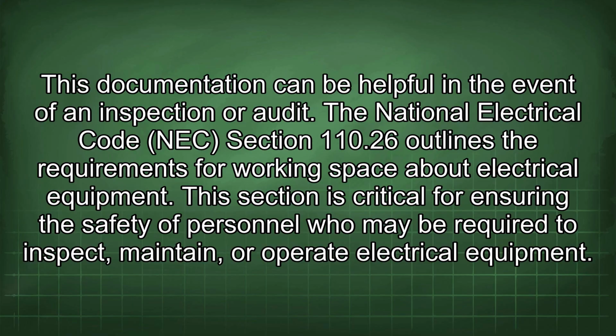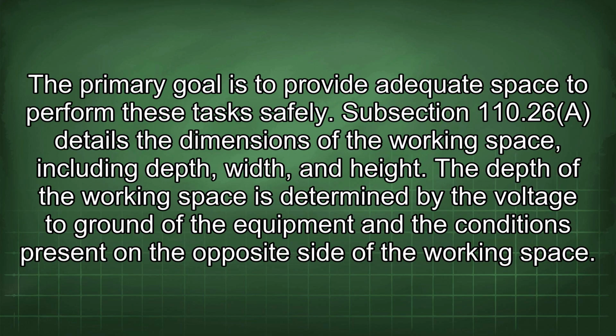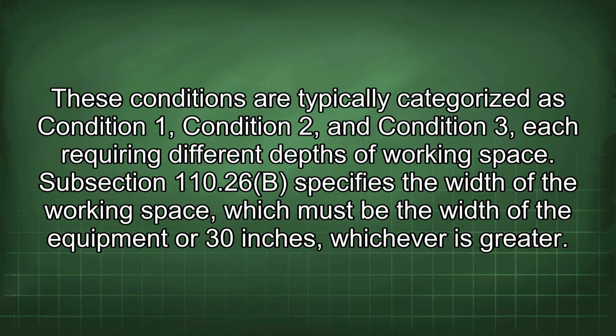The National Electrical Code, NEC Section 110.26, outlines the requirements for working space about electrical equipment. This section is critical for ensuring the safety of personnel who may be required to inspect, maintain, or operate electrical equipment. The primary goal is to provide adequate space to perform these tasks safely. Subsection 110.26a details the dimensions of the working space, including depth, width, and height. The depth of the working space is determined by the voltage to ground of the equipment and the conditions present on the opposite side of the working space. These conditions are typically categorized as Condition 1, Condition 2, and Condition 3, each requiring different depths of working space.